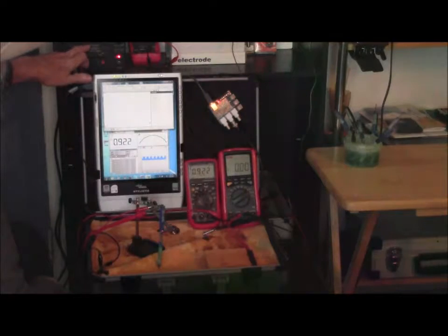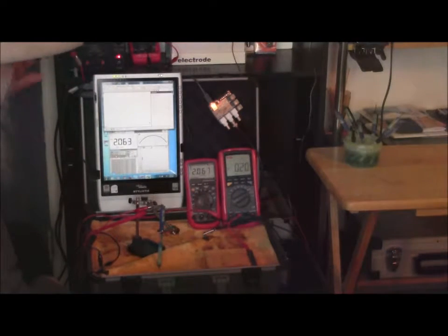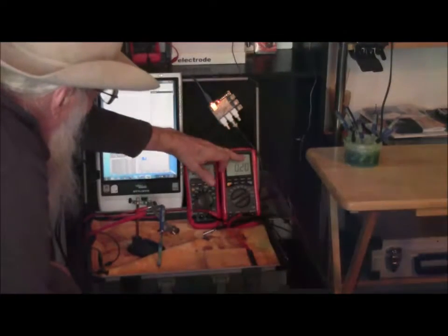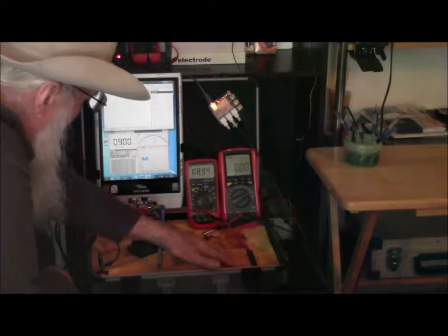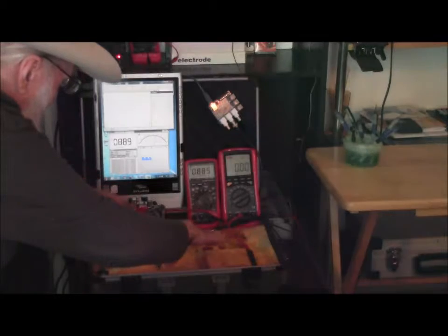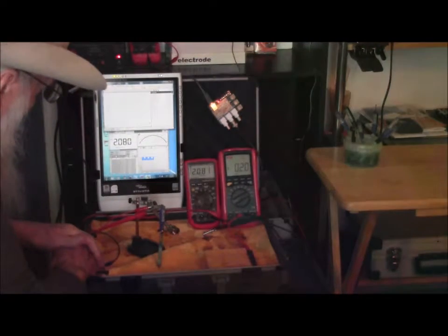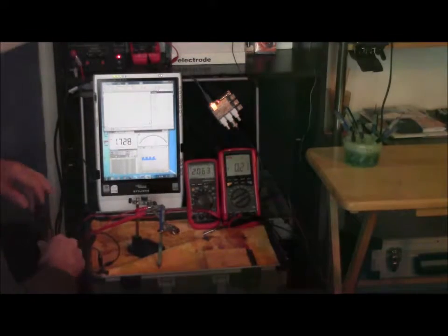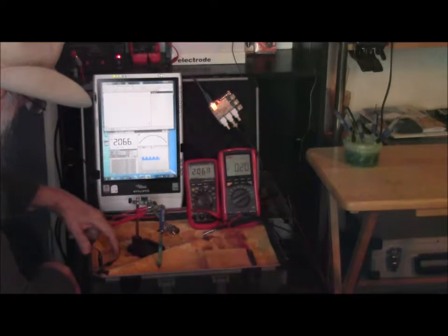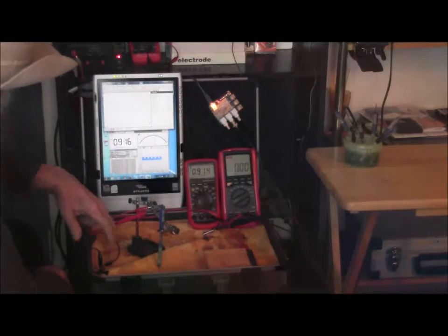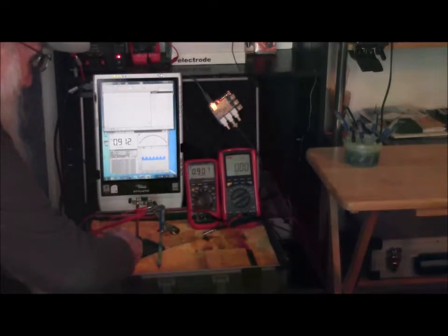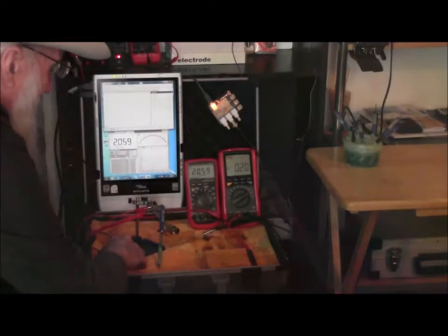We have a transformer rectifier with settings for voltage and amperage. The charges go from the transformer rectifier through this microammeter to the ground bed. They then disperse throughout the damp cloth that represents the ground, and they return to the transformer rectifier through connections at this drain point to the negative of the transformer rectifier, at the same time passing through coating faults on this buried pipeline.